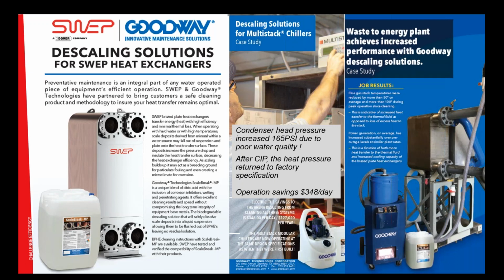Even the manufacturers of plate and frame heat exchangers recommend cleaning in place as the first step when fouling hits. The reason being that the economy of closing everything down and opening up a heat exchanger to clean it out mechanically is such an economic hit of downtime and manpower that cleaning in place makes much more economic sense.